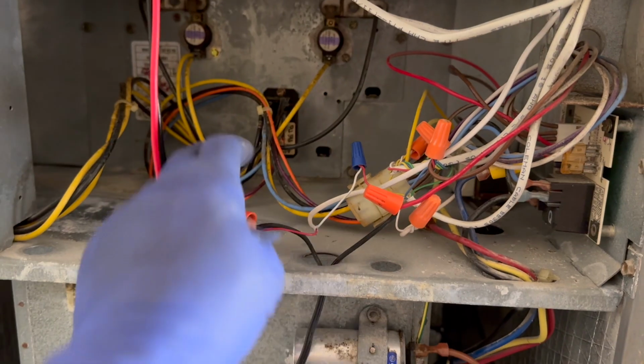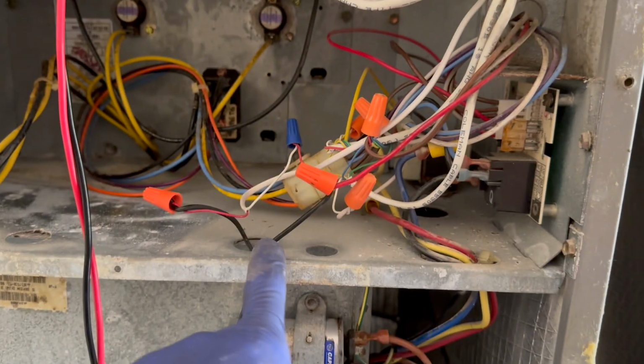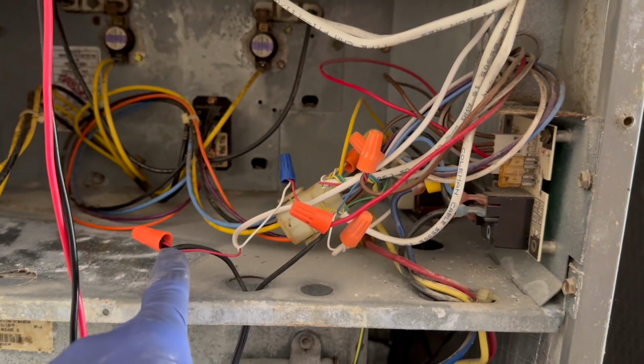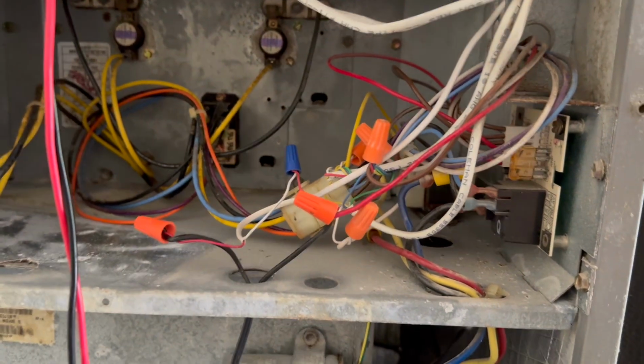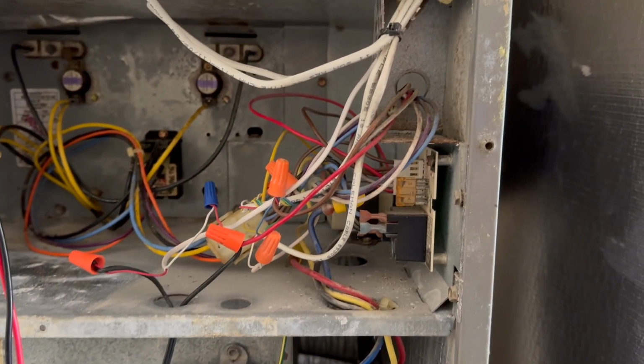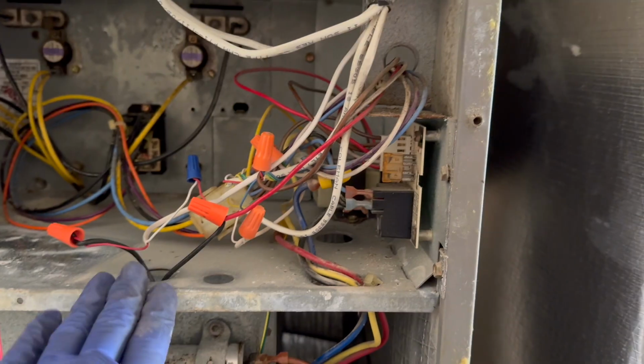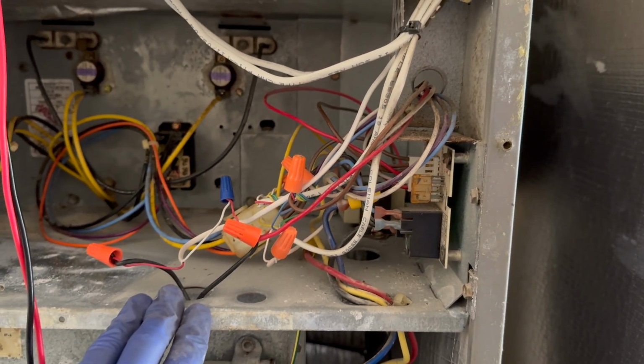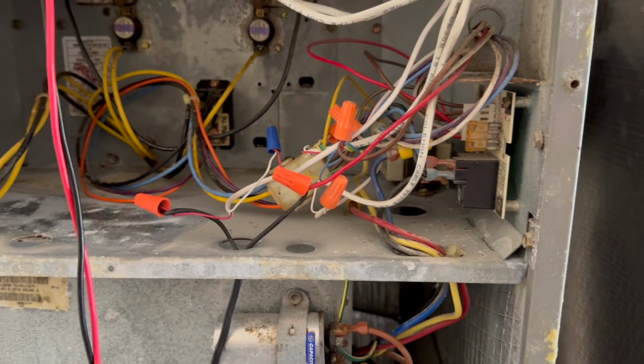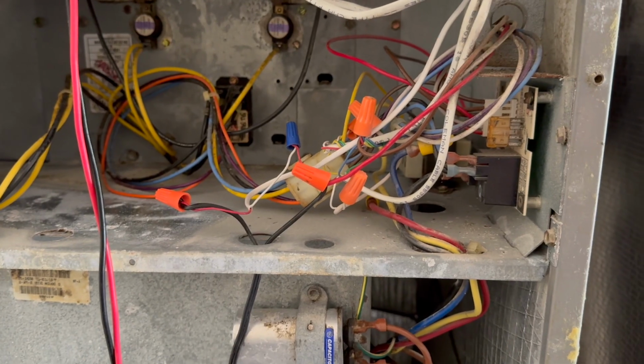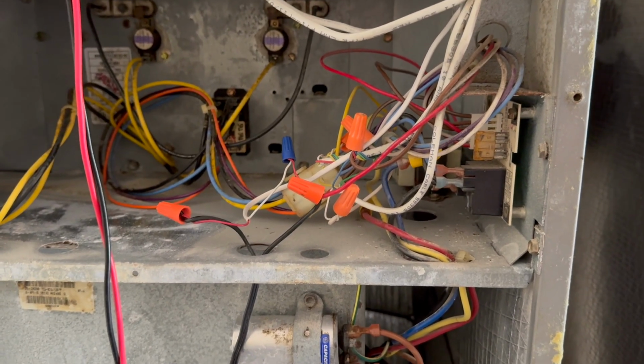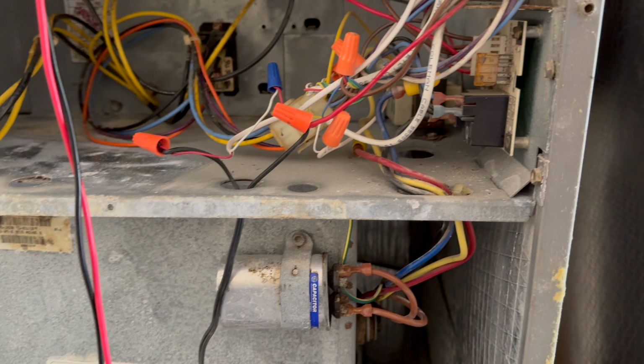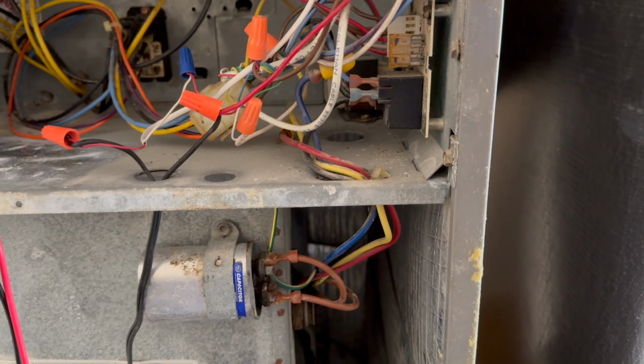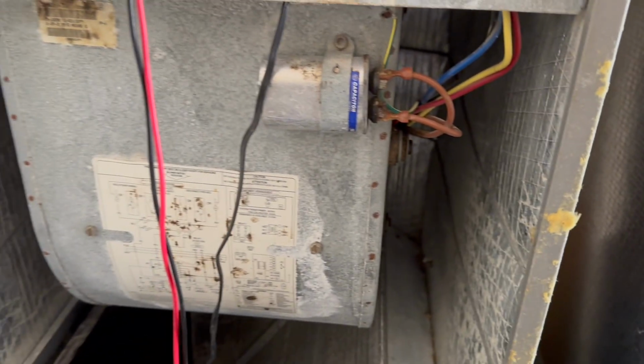Since I have this in series, every time the float switch is activated, I kill the power going to the thermostat. Now, the reason I did not come to this right off the bat is because this AC was off for a while, so it didn't trigger my mind that it could be a float switch since it hasn't been used. But there could be many reasons, you know, the float switch could go bad, and things like that.